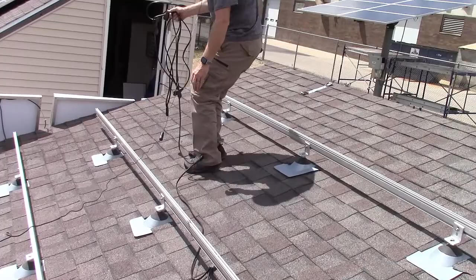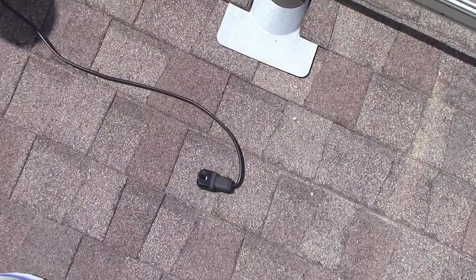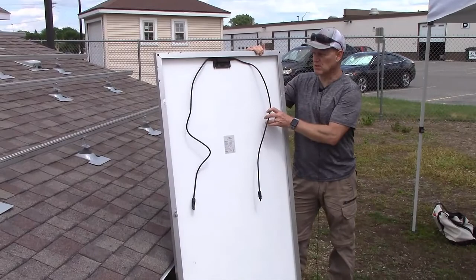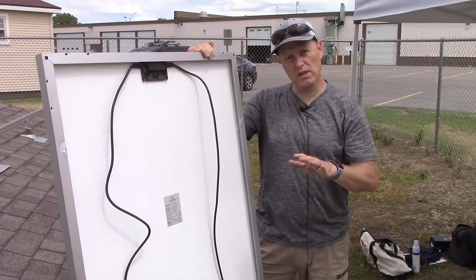And then by laying out this cable on the rooftop, we get a sense of where our module connections need to be. This is our limiting factor, the length of this cable. So we'll be able to place our microinverters and then our modules in the spots that they need to be on our roof. Because the positive and negative leads on the module are only about 3 feet long each, we need to make a plan for how we're going to lay the modules on the rooftop before we get onto the rooftop. So we'll draw out our plan while we're on the ground, and then we'll implement it as we put our modules on the roof.